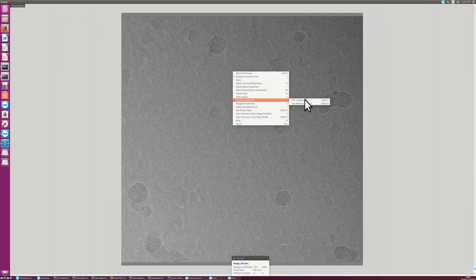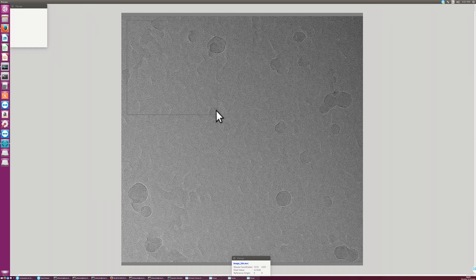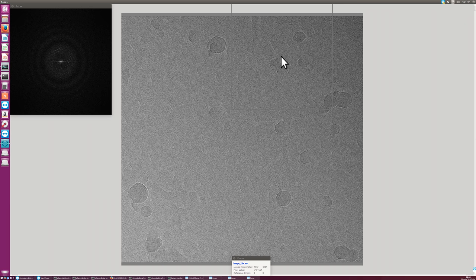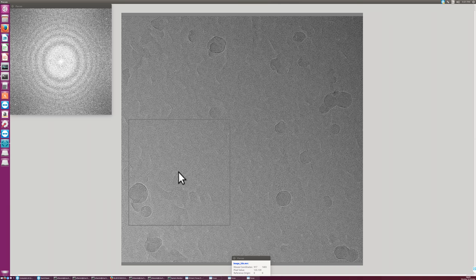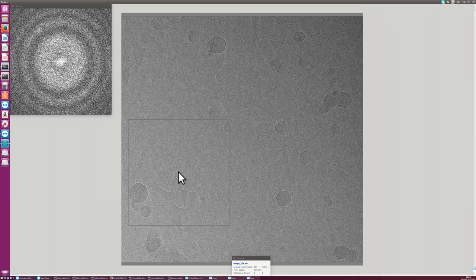And with that I can make a little box here, and then when I click with the right mouse button, it calculates the Fourier transform where we just are. And with the numbers on the keyboard, 1, 2, 3, 4, 5, 6, 7, 8, 9, I can adjust the contrast of this. So with 9 I see the Thon rings, and with 3 or 2 or 1 I see the lattice spots. But at the moment I want to look at the Thon rings. With 8, for example, and I can zoom this up with plus and minus on the keyboard, but I stay with the normal view.